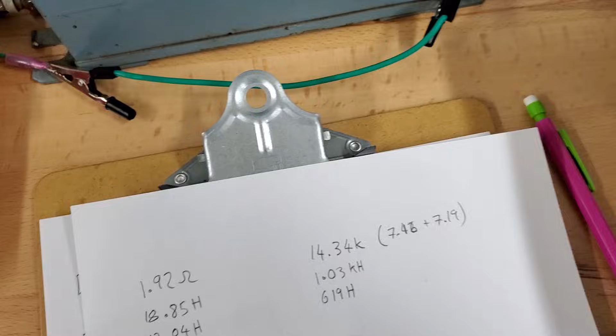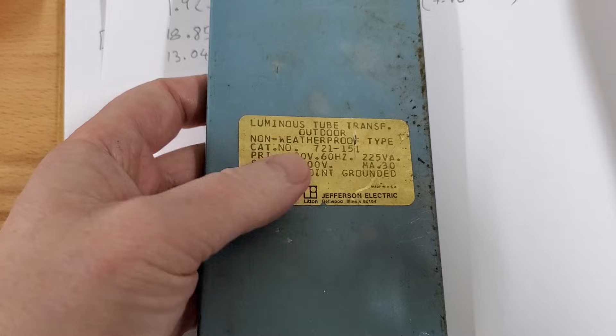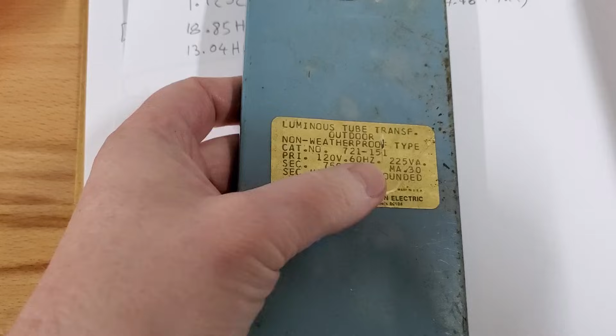So this is ultimately a magnetically shunted device, because the neon sign that it's connected to will have a negative resistance characteristic. Once it's ignited by the open circuit voltage, and it ionizes the gas inside, then it will look like a fairly low impedance. The exact resistance, you can do the math on that. But the open circuit output voltage of this transformer when fed with 120 would be 7,500 volts, I believe. Is that what the compliance plate says here? Yes, 7,500 volts. It says 225 VA as well, and it's a 30 milliamp rated transformer.